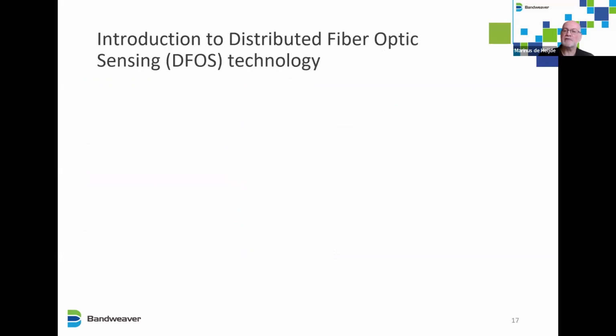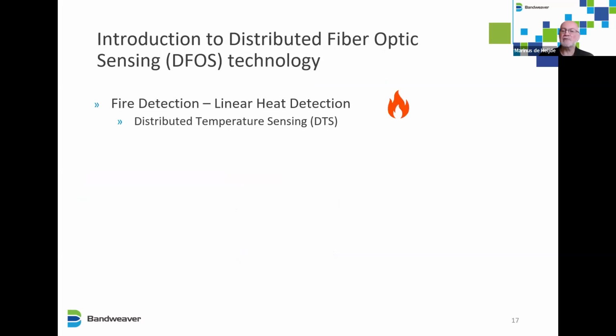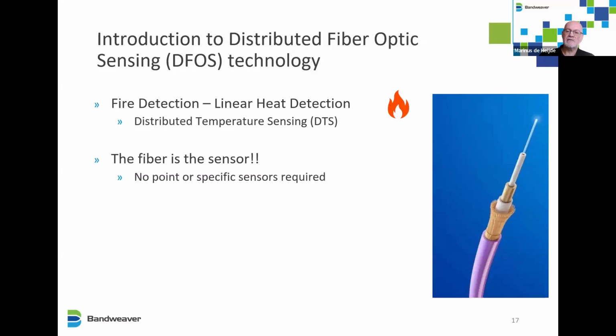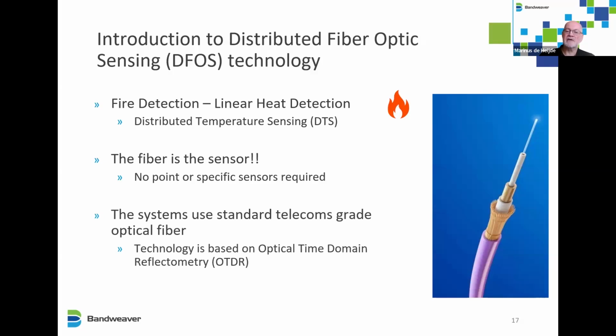So an introduction again to distributed fiber optic sensing, the technology itself. We're dealing with something called distributed temperature sensing, where the fiber is the sensor. We do not need any point or specific sensor. The main thing to remember here is that the whole fiber cable senses. And the system uses standard telecoms grade optical fiber. The technology is based on something called OTDR, which stands for optical time domain reflectometry.